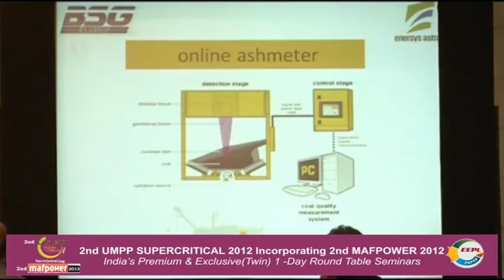This is the schematic of the ash analyzer, where you can see the source positioned down below the conveyor belt, and the rays pass through to the detector stage. From there it goes to the control system, and from there it can be accessed on the server. From the server, anybody authorized can access the data. This gives us the quality and quantity of coal passing through the conveyor belt to the boiler at any given point in time.